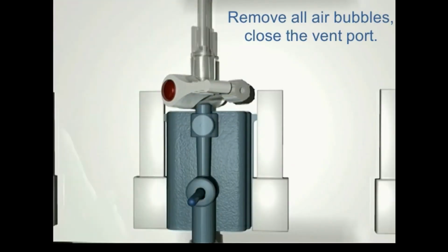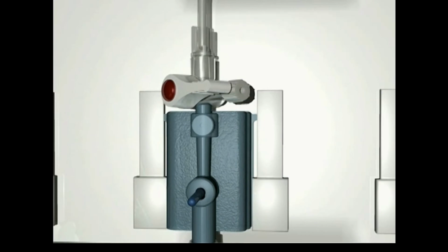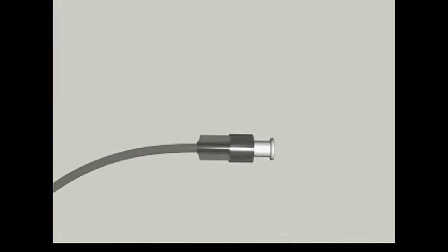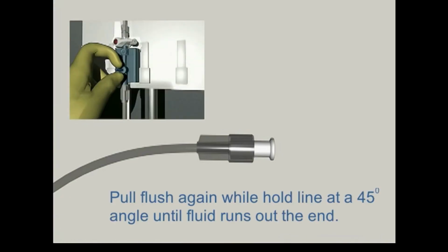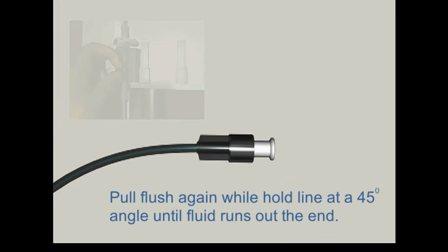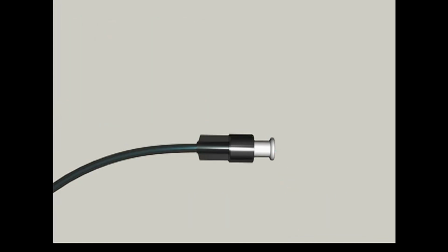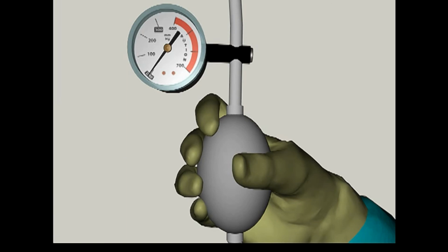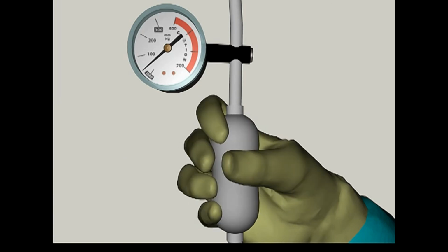Close the vent port by turning the stopcock towards the cap. Holding the pressure tubing in an upright 45-degree angle, pull the snap tab to flush the remaining part of the line through the end of the tubing. Step 5. Fast flush the TrueWave transducer system.